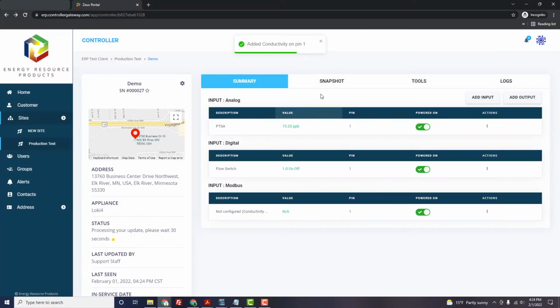A confirmation, called a toaster, will appear, confirming the addition. You will note the newly added input is not configured. The status indicator will turn yellow, indicating the controller is being set up with the new information. The controller is programming the slave address on the probe. While yellow, you will not be able to make any additional edits to the controller.